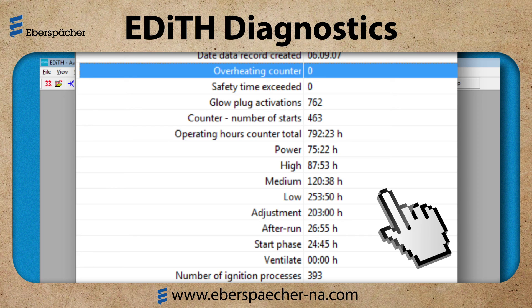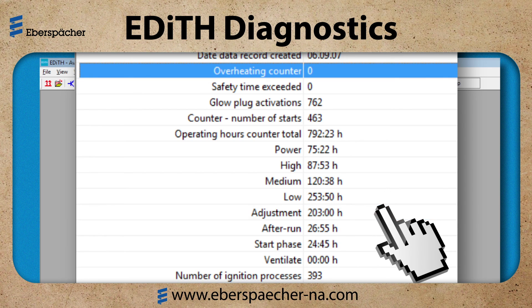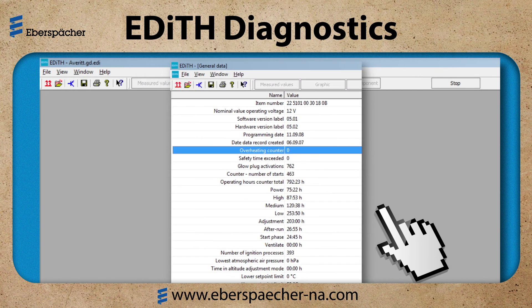Below the operating hours is adjustment, or standby. This is when the heater is active but the burner is not in operation. This heater has spent about 25% of the time waiting for it to cool down, and then the burner will restart. This concludes the general data test. I need to record this information.